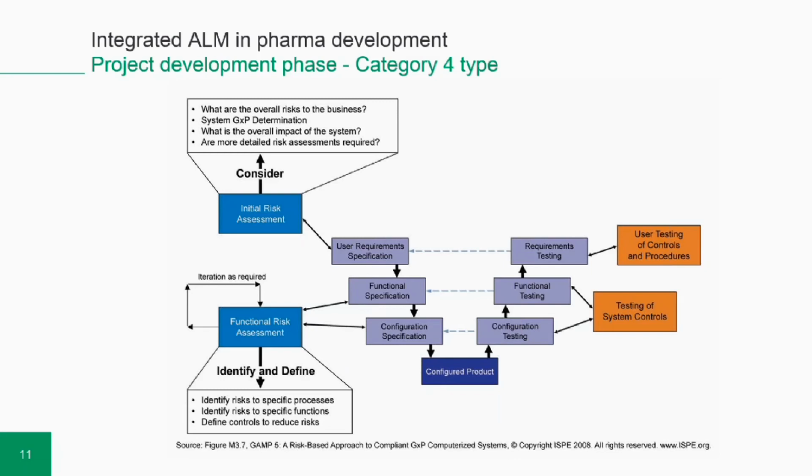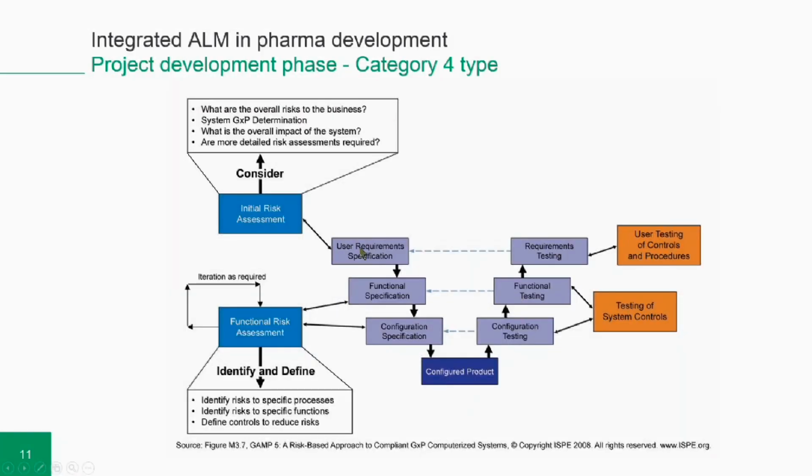In a more complex structure, when the software is category 4, containing configurable software, more levels of specifications have to be created. And again, this kind of activity is already shared with the supplier, which is also a target of GAMP 5: to share either the specification activities or the verification activities between the end user and the suppliers. The regulated companies themselves should decide, based on required levels of specification and verification, what activities can be shared on what level with the suppliers.